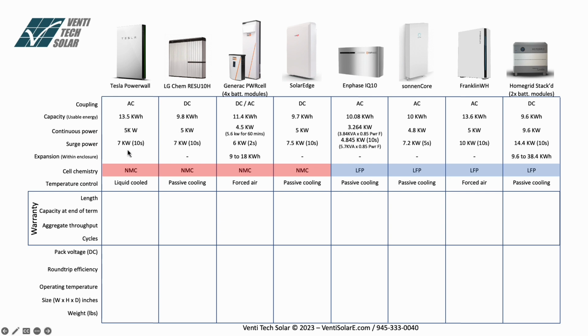As far as surge power, 7 kilowatt for 10 seconds on Powerwall, 7 kilowatt for the LG Chem, 6 kilowatt for 2 seconds on the Generac, 7.5 for 10 seconds the SolarEdge. Again, we have to calculate 4.845 for 10 seconds on the Enphase, 7.2 on the Sonnen, 10 kilowatt on the Franklin for 10 seconds, and 14.4 on the Home Grid, which is a really high number. As far as expansion, within the enclosure, you can expand the Generac from 9 to 18 kilowatt and the Home Grid from 9.6 to 38.4 with more layers sandwiched in the stack.